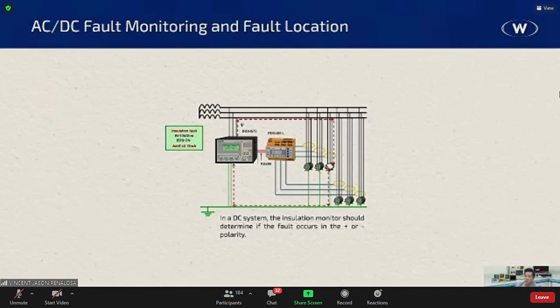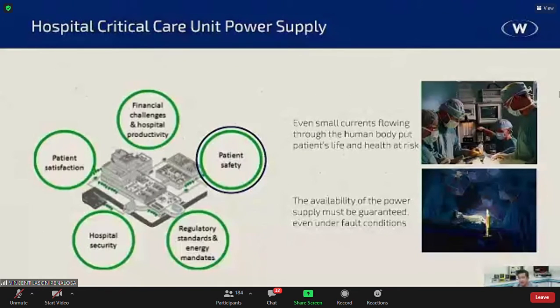Okay, so we now go to the hospital critical care unit power supply. Of course, there are a lot of issues for hospitals, no? And all we're going to be dealing with right now is patient safety. Under patient safety, one of them is patient security as well. Electrical safety is one of them, and other safety stuff. Why is patient safety very important in hospitals, particularly for critical care units and neonatal care? It's because even the smallest currents flowing through the human body put the patient's life and health at risk. And of course, the availability of the power supply must be guaranteed even under fault conditions. And that's the main reason why they're deploying ungrounded systems for operating theaters.